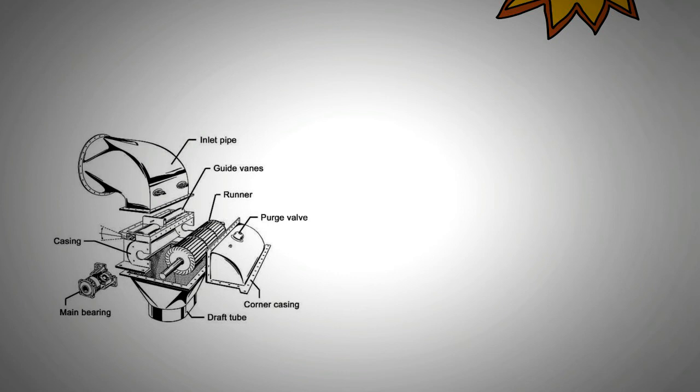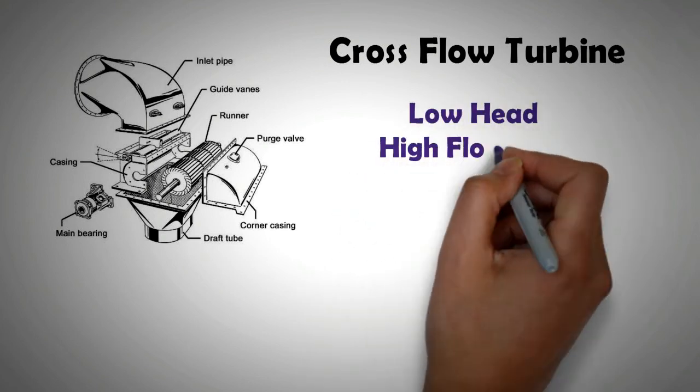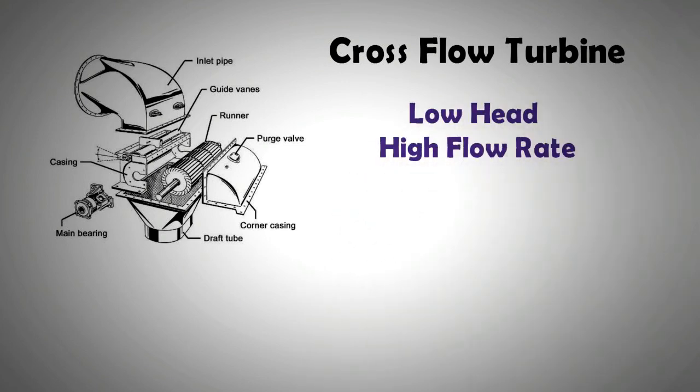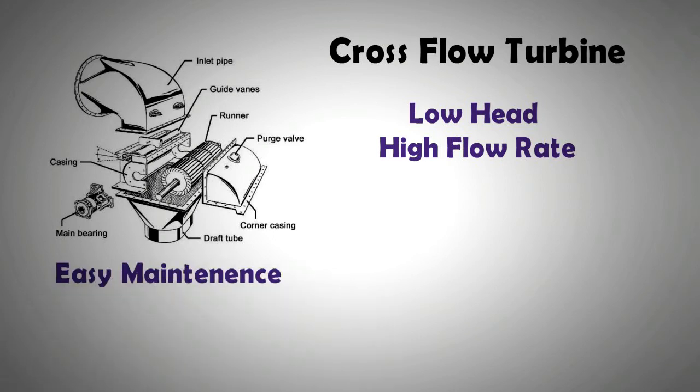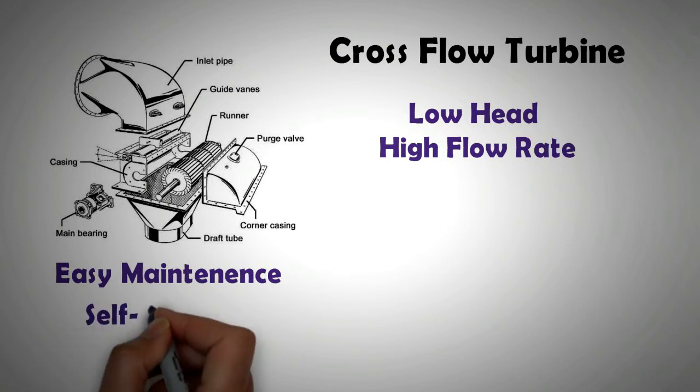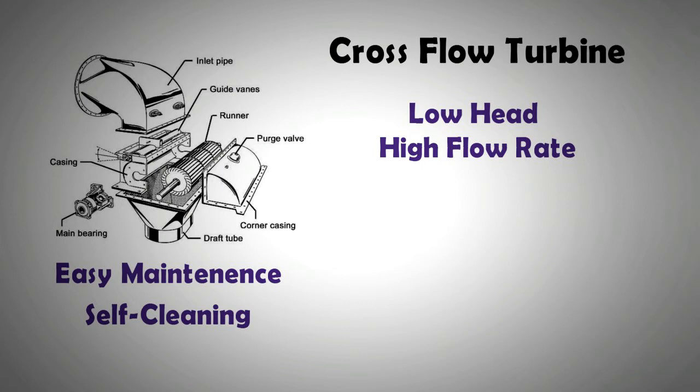And lastly, there is the cross flow turbine or the Banki turbine. It is a slow moving machine which is well suited for locations with a low head of water but with high flow rate. Being a slow mover, the turbine is easier to maintain as the bearings don't need to be replaced often. Furthermore, the turbine is self-cleaning and gets clogged up less frequently compared to other turbines. The efficiency of cross flow turbine and the Pelton wheel is lower than that of Francis turbine and Kaplan turbine.